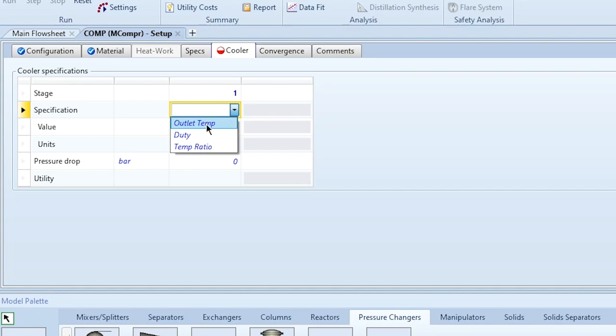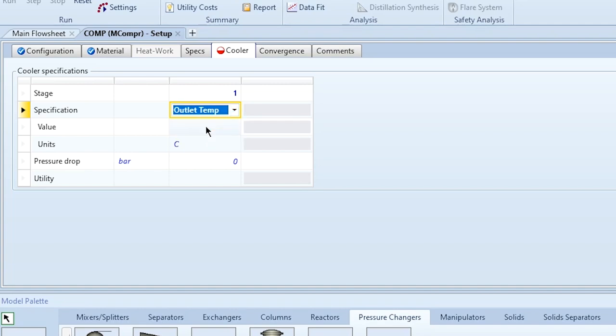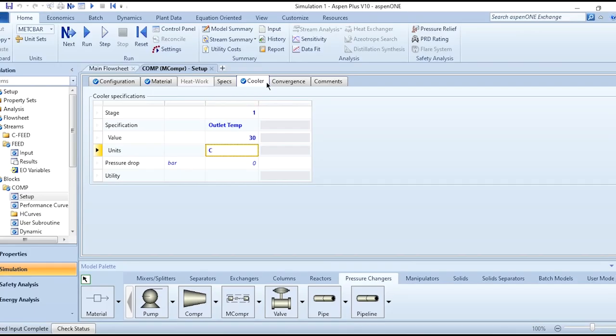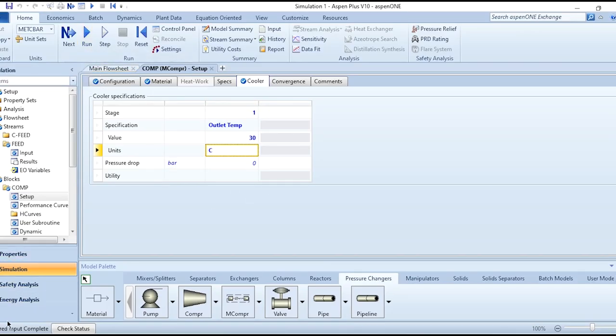The cooler specification options are outlet temperature, duty, or temperature ratio. The values correspond to the temperature of the process fluid — in this case methane — not the cooling water. For example, set the outlet temperature to 30°C. Once all specifications are given, the Run button becomes active. Click Run.